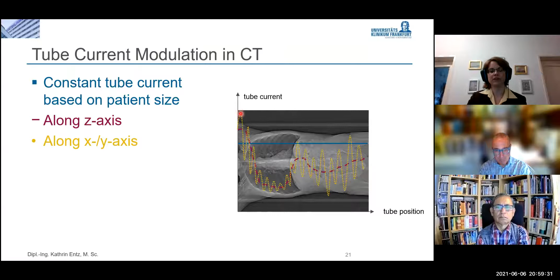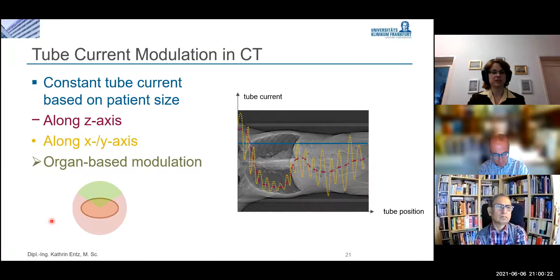And the last type of tube current modulation would be an organ-based modulation. You cannot see this in this image here, but instead you have to look at this small graph. The dose is reduced during a certain angulation of the tube to reduce the dose on very radiosensitive organs, for example, the breast or the eye lenses of the patient. And to keep the image quality constant, the dose that was taken away from this part is then added elsewhere. So during a whole rotation of the scanner, you would have the same CTDI as you would have without the organ-based modulation.